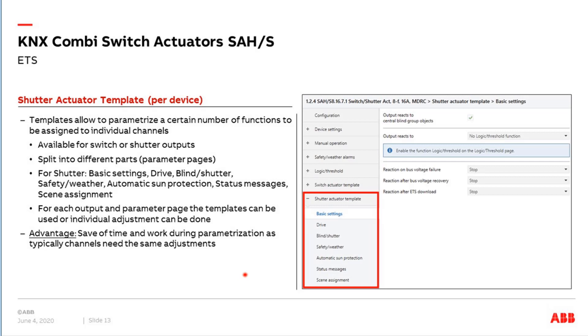Templates are also available for shutter functionality. A template means you create a parameterization for different parameter pages, and then you can decide later whether that parameterization is valid for other channels — maybe all channels in the device. You can choose the template instead of parameterizing each channel individually with the same parameters, saving a lot of time. In each channel, you decide whether to use the template or have individual programming. The application is split into seven parts.